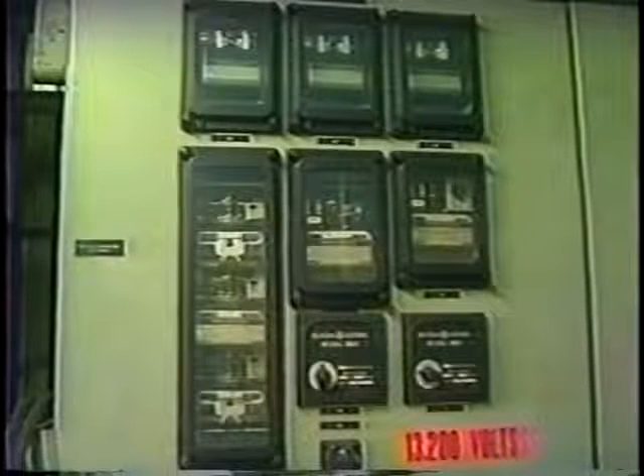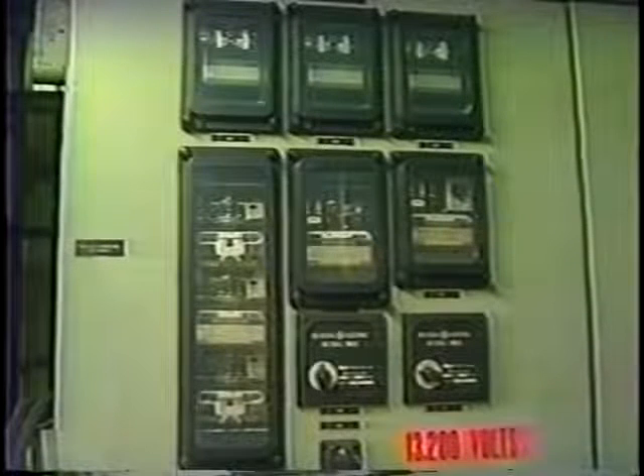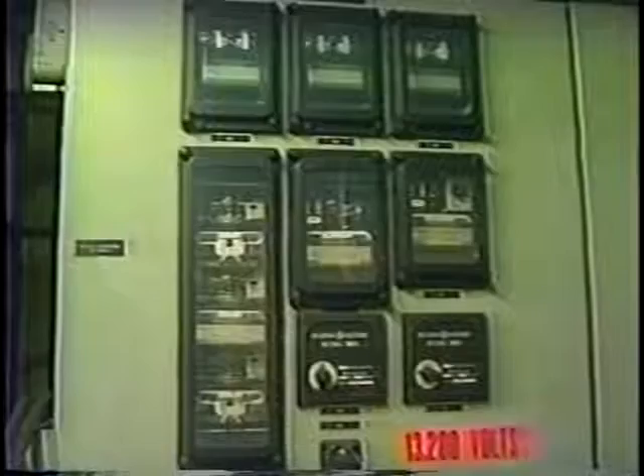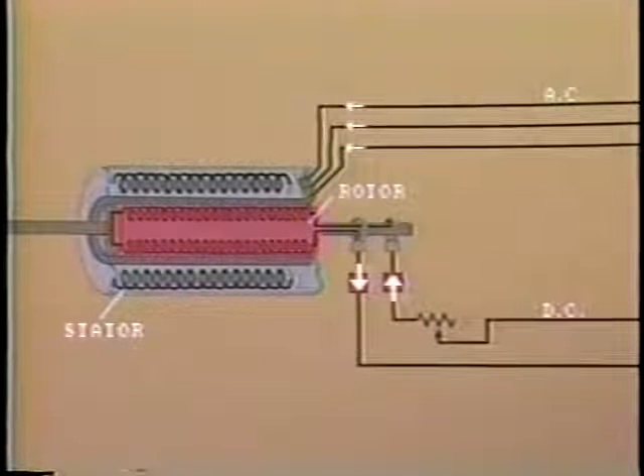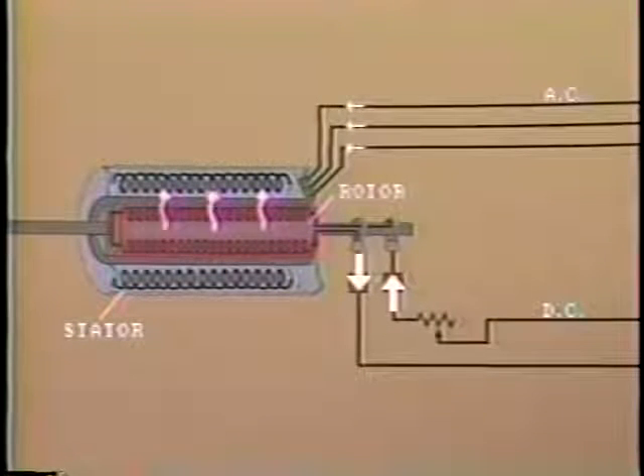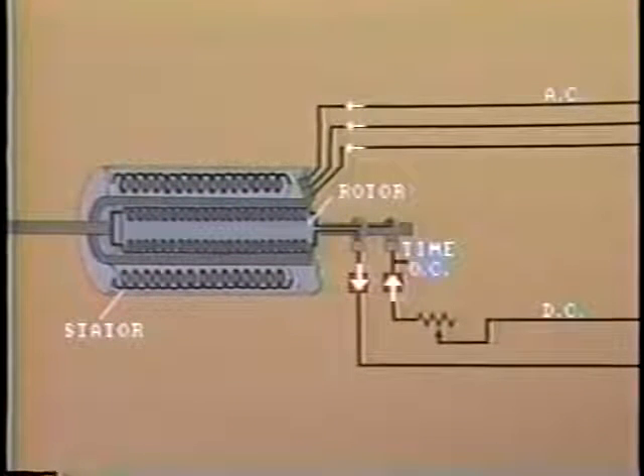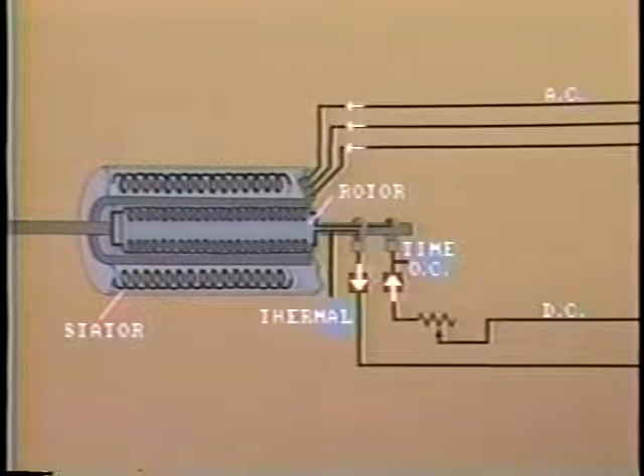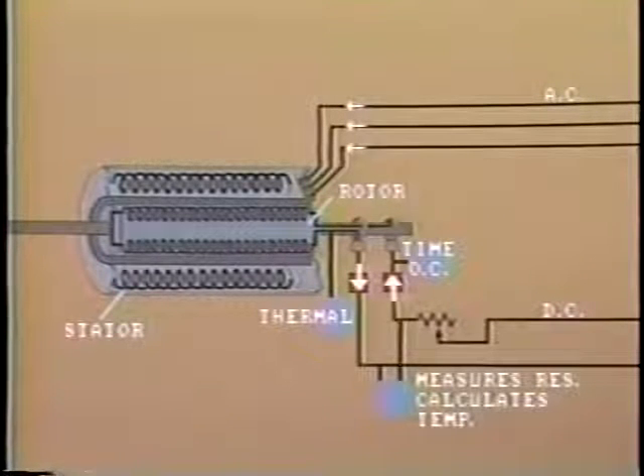Generally speaking, protection for the synchronous motor is similar to that for the induction motor, but with the addition of a few special relays. One particular condition to protect against is that of overexcitation of the rotor. Conceivably, automatic power factor control or voltage control could result in excessive DC current flowing through the rotor field windings and so lead to overheating of the rotor. Protection is provided by either a time overcurrent relay or a thermal bimetallic relay connected into the field winding circuit. Another, more direct method measures the resistance of the field winding and from this calculates the temperature. These relays are wired to sound an alarm or perhaps in an unattended station to trip the unit.